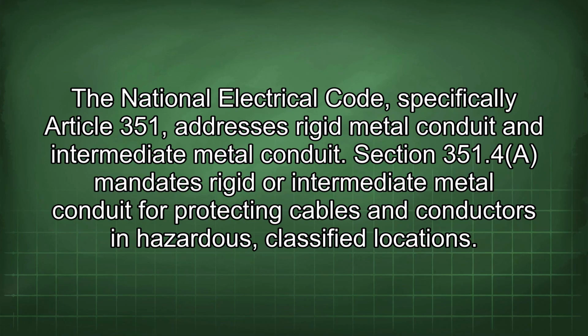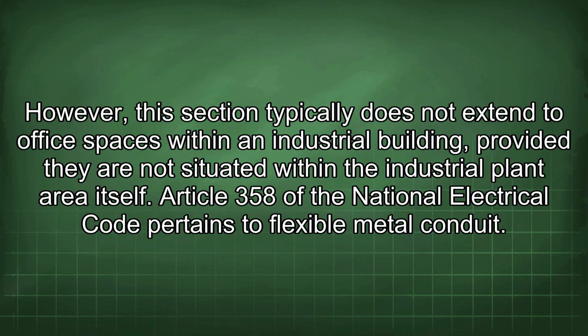The National Electrical Code, specifically Article 351, addresses rigid metal conduit and intermediate metal conduit. Section 351.4 mandates rigid or intermediate metal conduit for protecting cables and conductors in hazardous, classified locations. However, this section typically does not extend to office spaces within an industrial building, provided they are not situated within the industrial plant area itself.